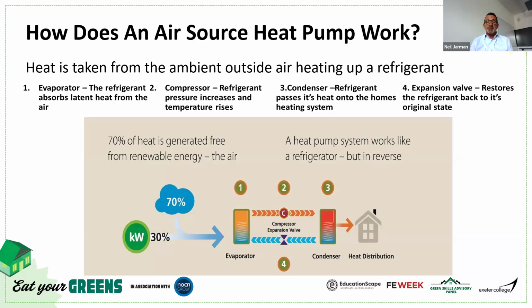So starting with how it works. With a heat pump, you're pulling the air across the evaporator, which is increasing the refrigerant temperature from a low temperature refrigerant to a higher temperature refrigerant. Then the compressor, number 2, compresses it to a very, very high temperature where all the molecules are tight and jumping together, so it really gets everything out of the refrigerant within the circuit. The condenser then takes that heat and transfers it indoors via that flow and return pipe to your cylinder, 3-port valve, and your heating system. And then number 4 is an expansion valve.